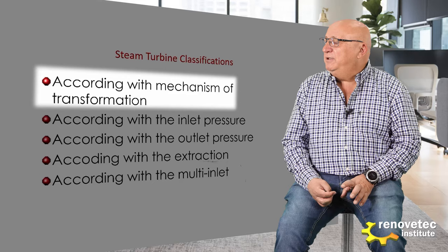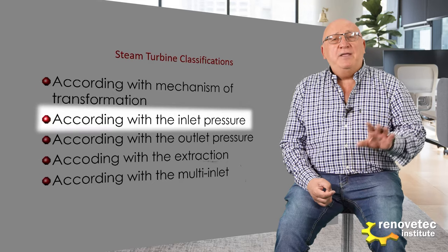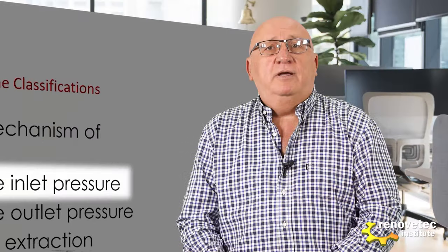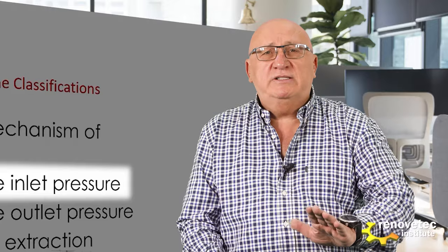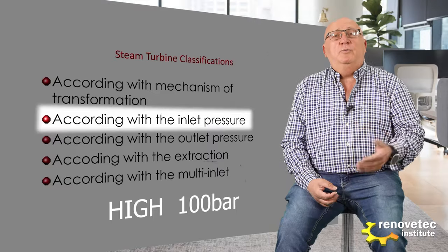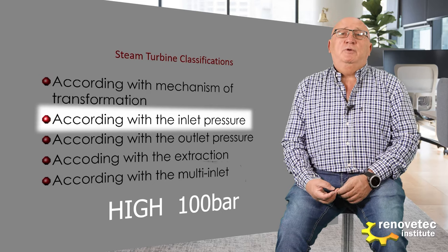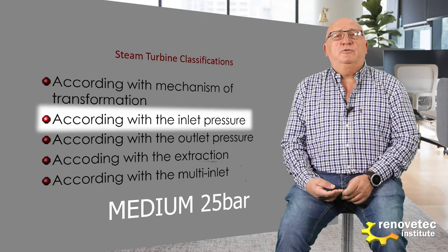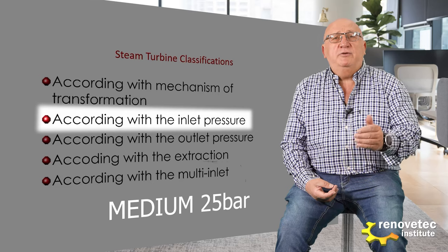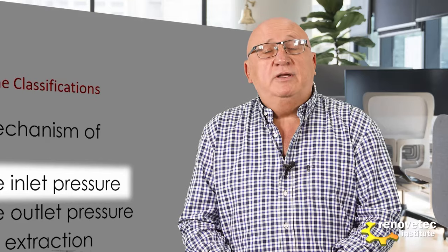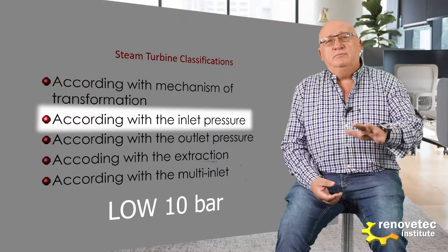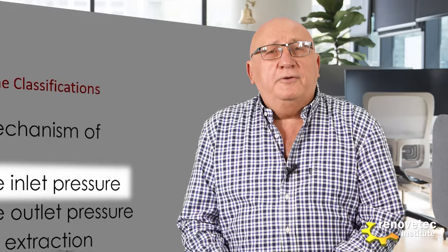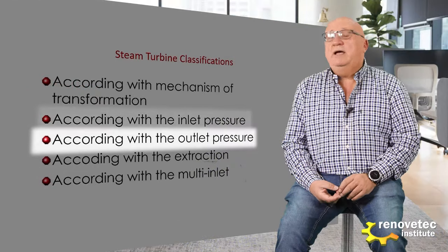The second classification is according to the inlet pressure. We have high pressure turbine, medium pressure turbine, and low pressure turbine. When the pressure is around 100 bar or more, we talk about high pressure turbine. When the pressure is around 25 bar, we talk about intermediate pressure or medium pressure turbine. And finally, when the inlet pressure is around 10 bar or less, we talk about low pressure turbines.